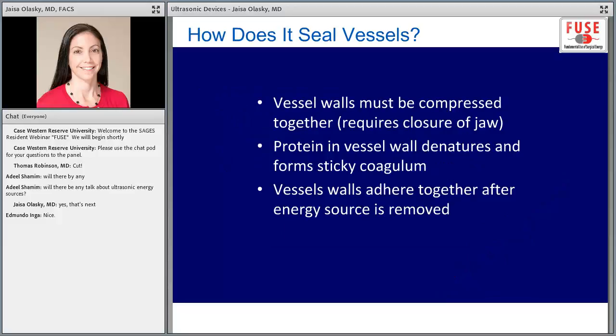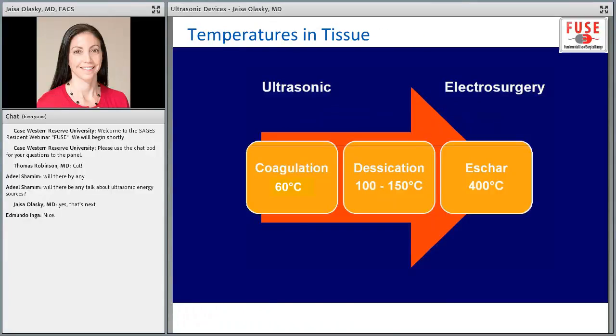Then we talk about the coagulation function. So how does it seal vessels? First of all, it's the coaptive coagulation, which was described also with the monopolar discussion. But in this case, it's obviously not with the RF energy, but with the ultrasound. So the vessel walls must be compressed together, so you have to close the jaw tightly. The protein in the vessel wall will denature and form a sticky coagulum. The vessel walls then adhere together after the energy source is removed, and that's how you get the vessel coagulation. In this talk, it mentions an upper limit of 5 millimeter vessels, although some of the newer devices do allow up to 7 millimeters.